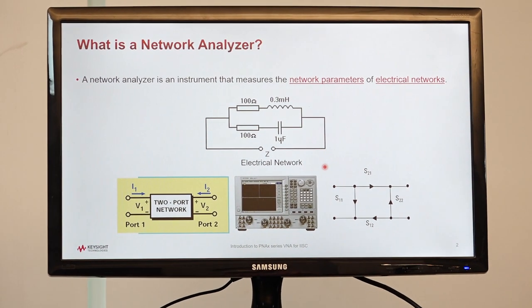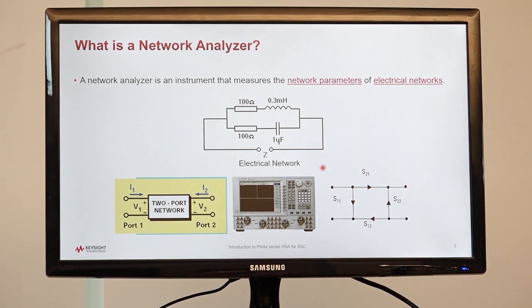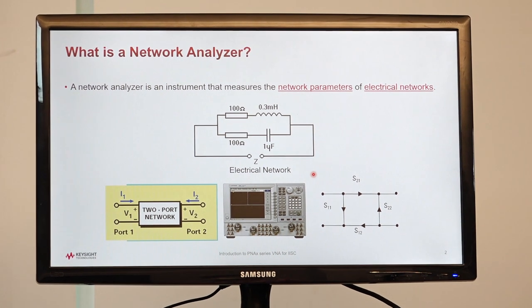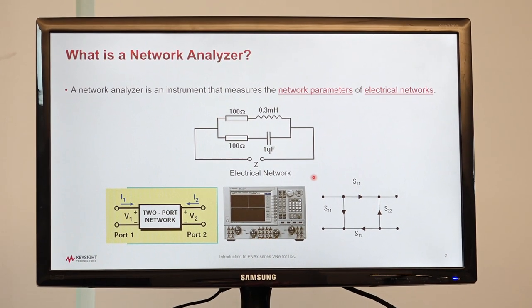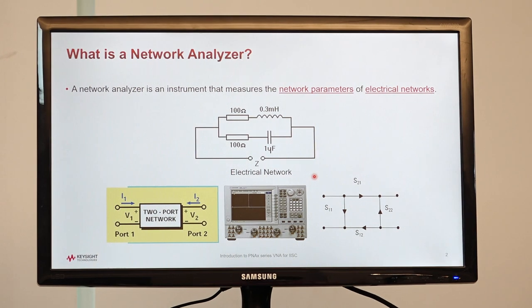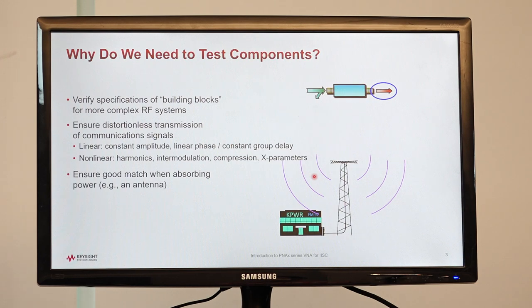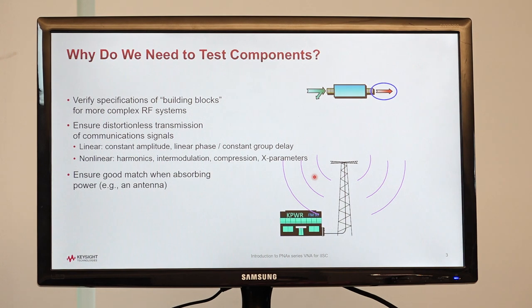A network analyzer is a general purpose instrument used for characterizing RF devices. Characterization can be as simple as insertion loss or insertion phase measurements, or as complex as noise figure or error vector magnitude measurements. These test components go into bigger systems, so we need to understand how each building block is behaving. Vector network analyzers help us characterize each of those building blocks.